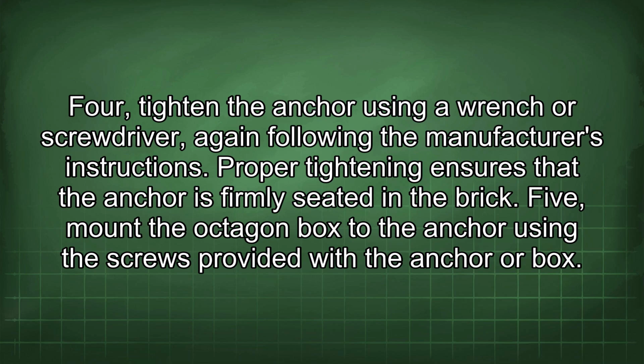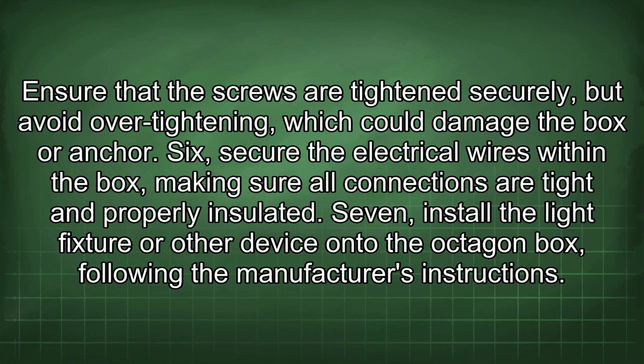Fifth, mount the octagon box to the anchor using the screws provided with the anchor or box. Ensure the screws are tightened securely, but avoid over-tightening, which could damage the box or anchor. Sixth, secure the electrical wires within the box, making sure all connections are tight and properly insulated. Seventh, install the light fixture or other device onto the octagon box, following the manufacturer's instructions.